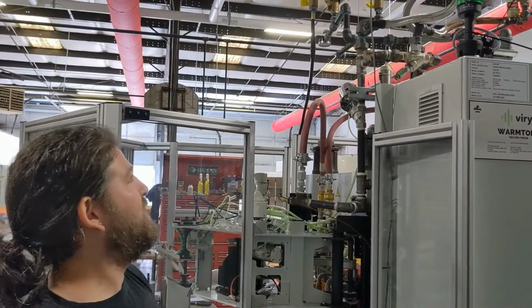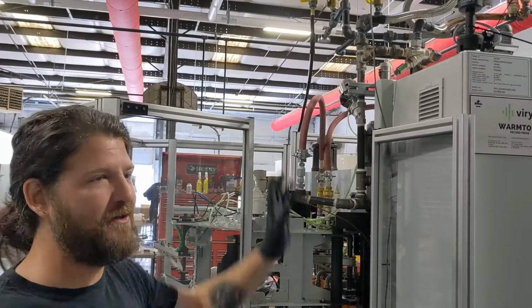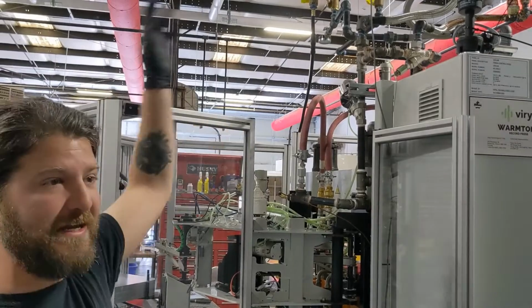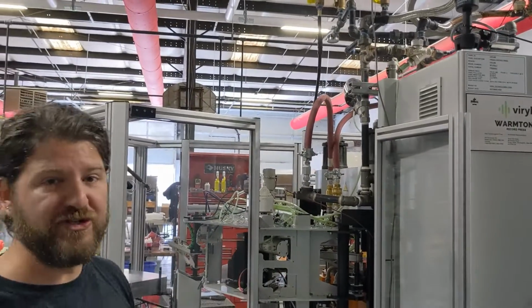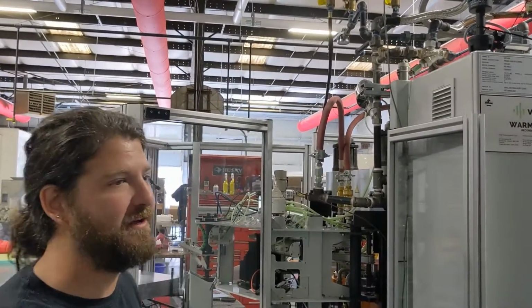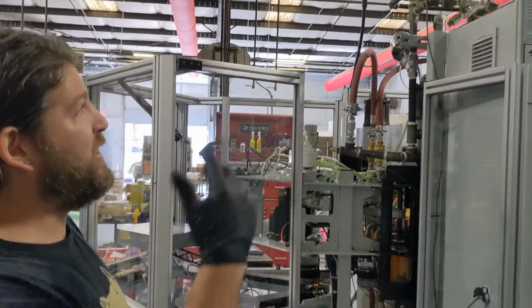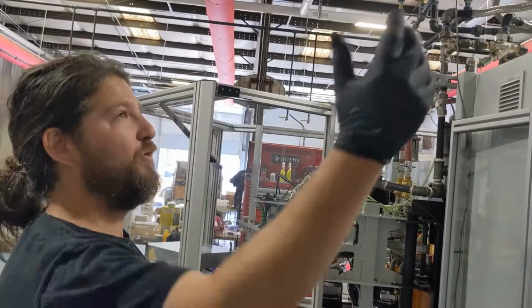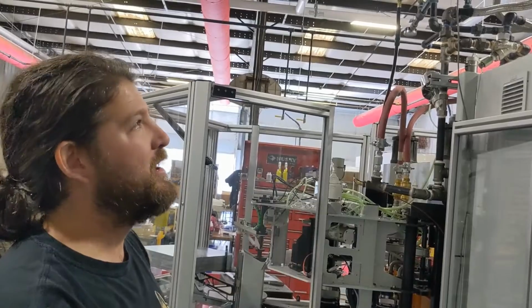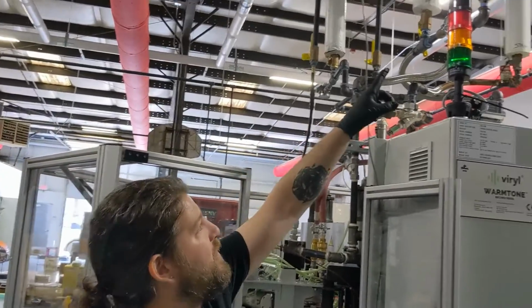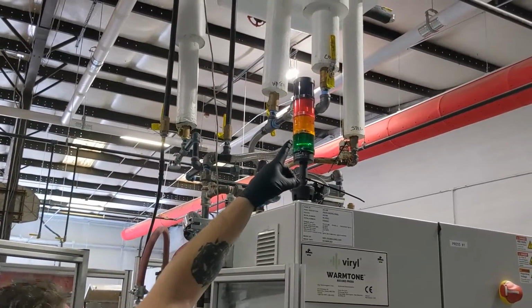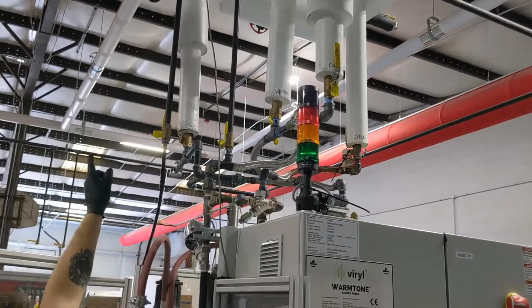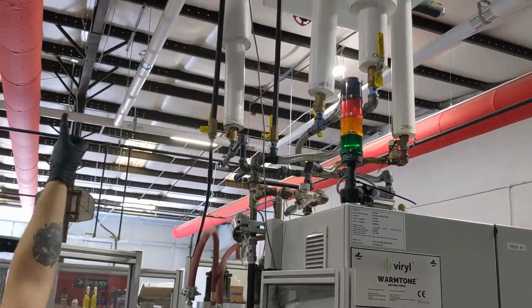So when it shoots out at 60 PSI from the press, it wasn't able to get into that pipe, and it was just sitting there, and our presses were overheating. Because we needed that 60 PSI and there was 120 coming in, we built a corner here, teed it off, made that little loop, added that globe valve, and tied it into here.